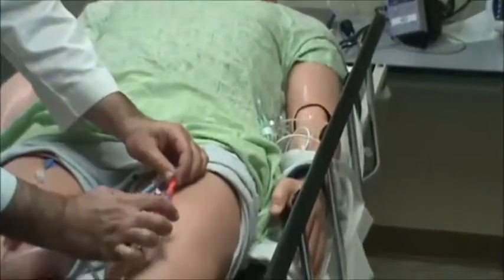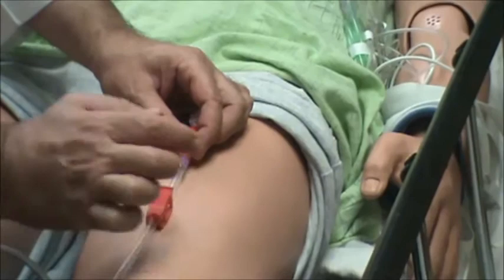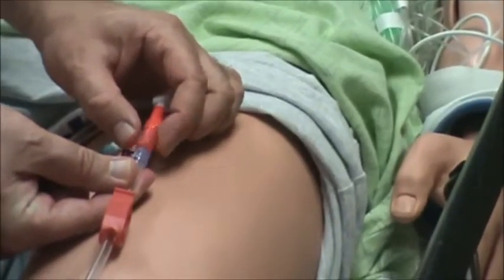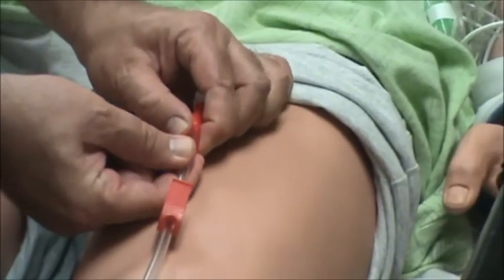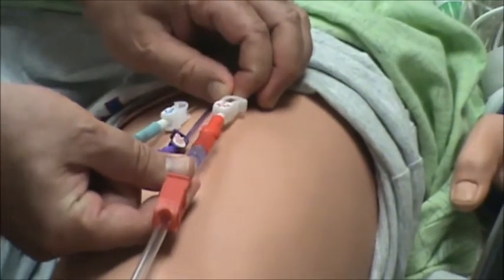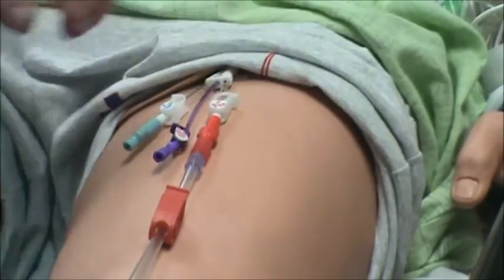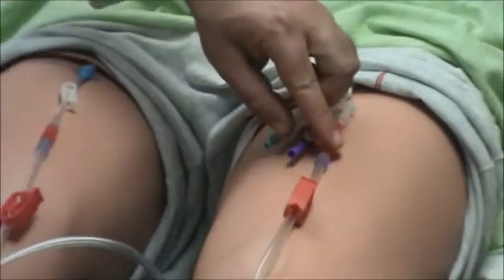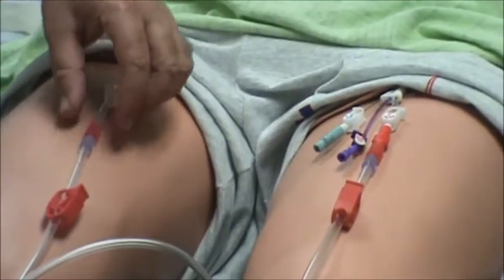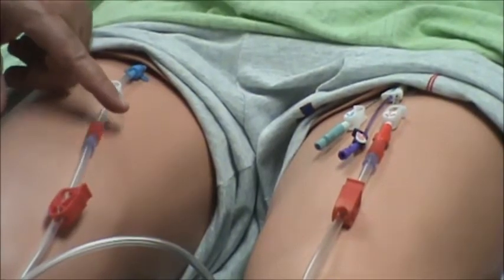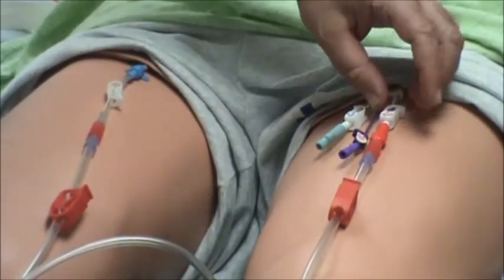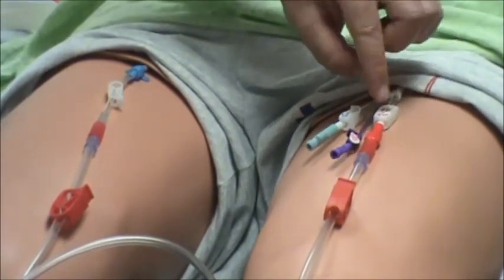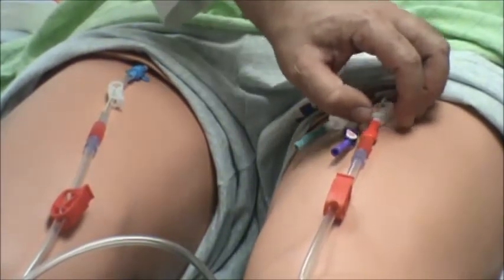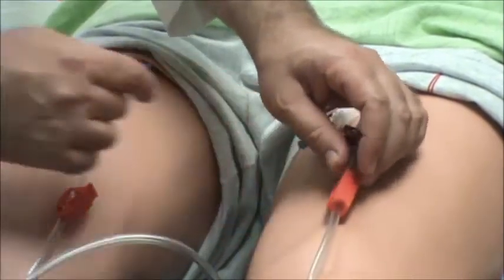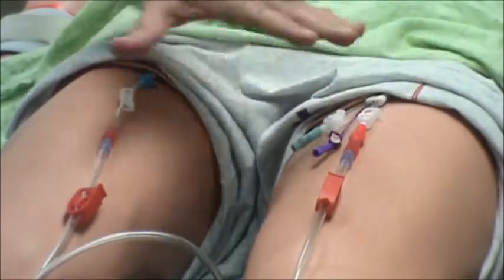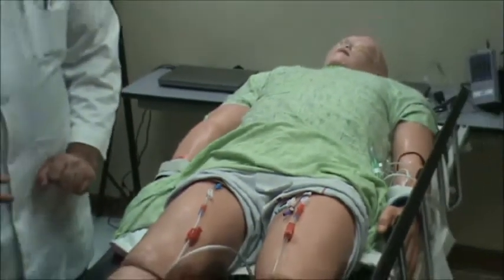So you insert it, and then this is a locking technology. That locking technology, it can be twisted, and when it's twisted, it truly secures the catheter and the tubing together so that it will not get loose. So this securing technology on both sides is a twisting technology that will lock the catheter and the tubing together. Then for safety reasons, there's also a clamp on the arterial side or on the venous return side here, as well as a clamp on this side. So once you connect all this, you have a closed circuit.